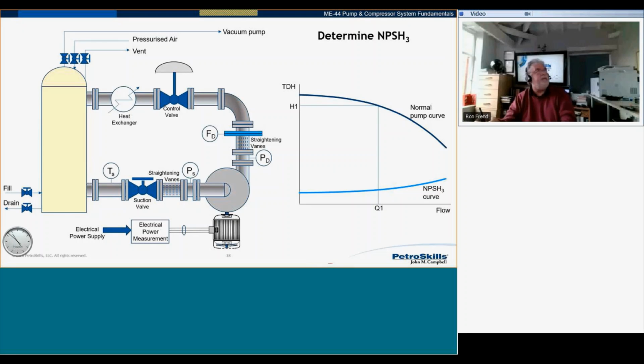And just one quick reminder just before we finish. I said that thing about NPSH. NPSH required, according to API 610, ISO 13709, is now called NPSH 3. And the reason for that is the definition of what is cavitation. And what the vendors do is they put their test pump in a test stand. The flow comes in here through the pump, back out through a control valve, through a heat exchanger, back into the tower. We control the pressure in here by either pressurizing or running a vacuum. We maintain the temperature in here nominally about 60 degrees Fahrenheit. And this will be fresh water.